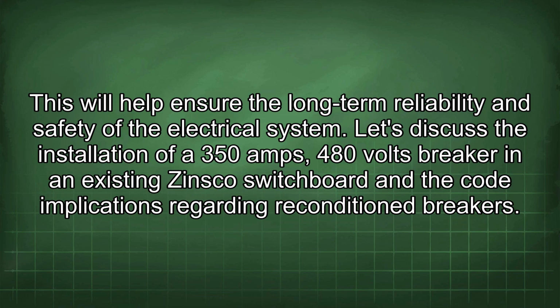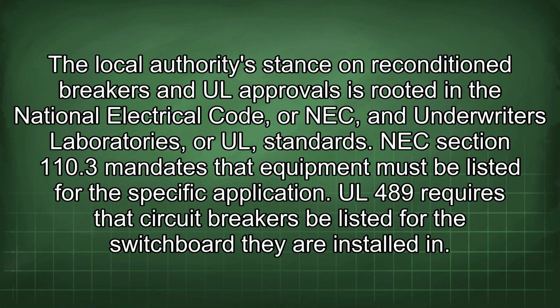Let's discuss the installation of a 350 amps, 480 volts breaker in an existing Zinsco switchboard and the code implications regarding reconditioned breakers. The local authority's stance on reconditioned breakers and UL approvals is rooted in the National Electrical Code, or NEC, and Underwriters Laboratories, or UL, standards. NEC Section 110.3 mandates that equipment must be listed for the specific application. UL 489 requires that circuit breakers be listed for the switchboard they are installed in.